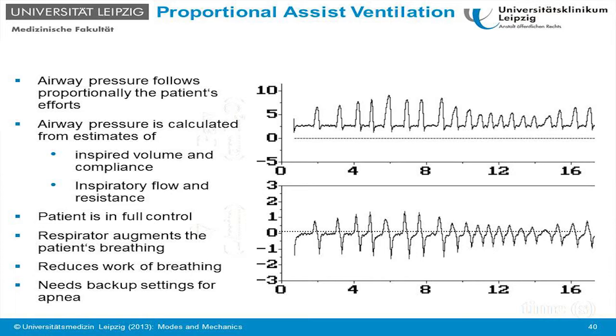And this you can see on this chart, the ventilator pressure and also the flow continuously change according to the patient's effort. The patient is in full control, and his own breathing is just augmented by the respirator. And the respirator only works to reduce the work of breathing for the patient, while the patient is doing his own ventilation as much as he can. However, this mode is obviously prone to apnea. If the patient stops breathing, then the ventilator would be there waiting for the next breath and not doing anything. So we need a backup ventilation that kicks in to overcome this phase of apnea, so the patient will not get bad desaturation.